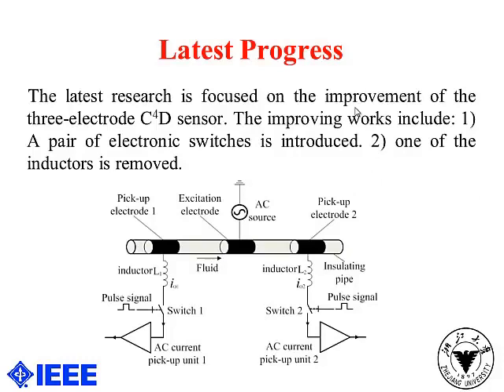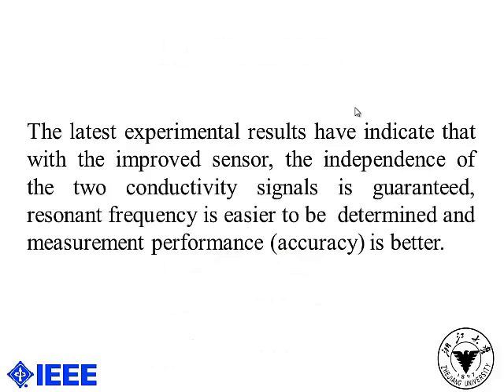At last, I will introduce the latest progress briefly. Our latest research is focused on the improvement of the three-electrode C4D sensor. The improving work includes: first, a pair of electronic switches is introduced; and second, one of the inductors is removed. Some experiments have been carried out with the improved sensor. The latest experimental results show that with the improved sensor, independence of the two conductivity signals is guaranteed, the resonant frequency is easier to determine, and measurement performance is better.